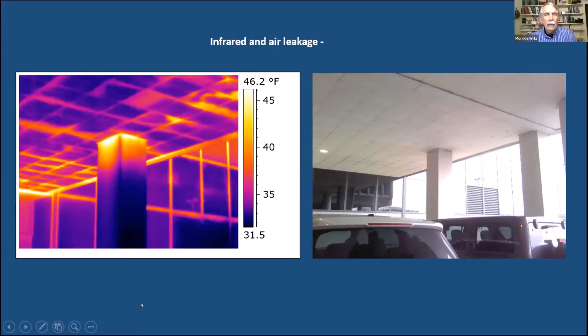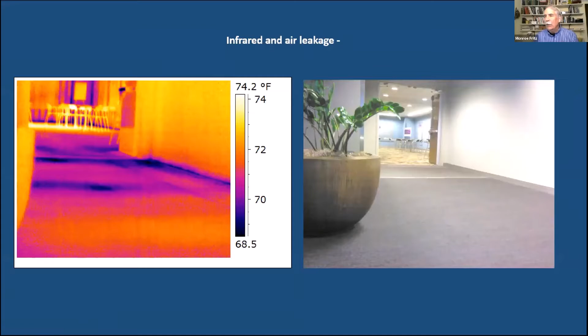There has never been a suspended ceiling on God's green earth that has been able to perform as an air barrier, so it's a mistaken design from the start. Our infrared on the left clearly shows heat coming out of the building. Up in the office above, where the original complaint was comfort issues and high utility bills, we see cold spots in the framework coming up from the parking spaces below. This is what infrared sees when you ask it to go looking for leaks in a building's air barrier.